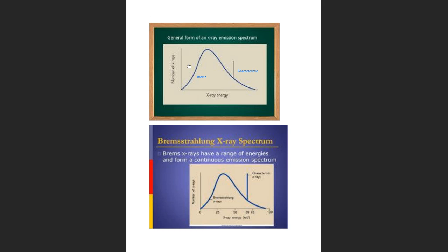And then filtration will affect efficiency, because filtration will decrease the quantity of that beam by taking out low energy X-rays, and that will also result in an increase in the quality of the beam.